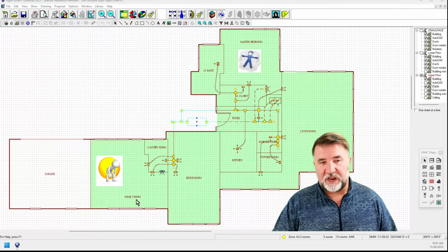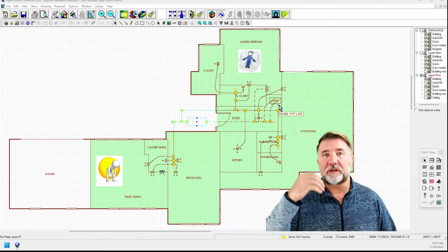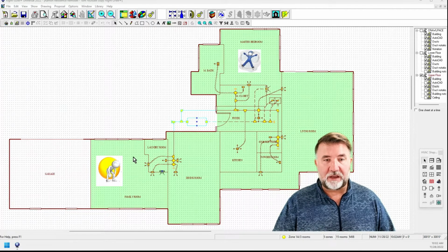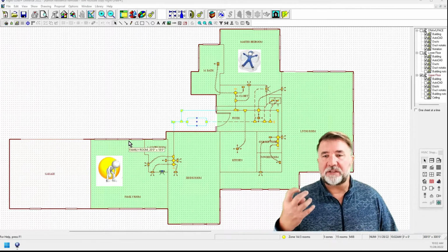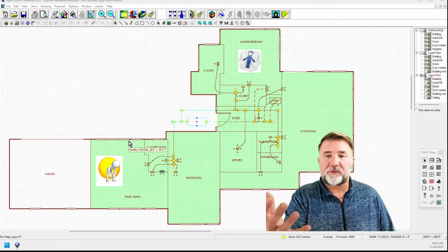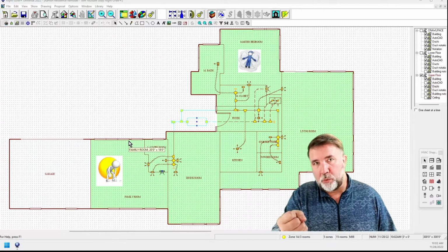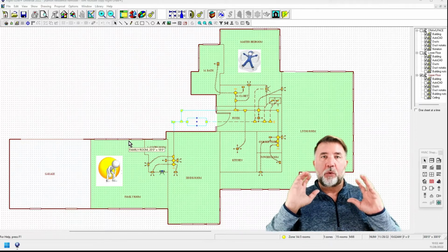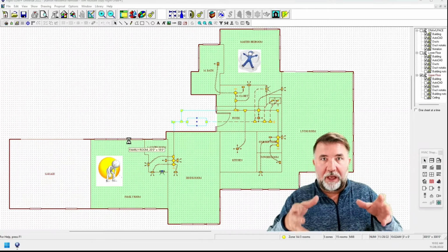But because this air over here has so far to travel before it gets pulled into here, for it to remove the moisture and the heat so that the temperature is cool, what's going to happen is, yeah, I'm pulling air from here and I'm conditioning it and I'm dumping it out here, but air conditioning is not just about pulling the heat out of that and just dumping cold air into another. In the rooms, you have to be able to remove the heat and humidity that's in that room. Otherwise, you're just dumping cool air on top of the hot, humid air.